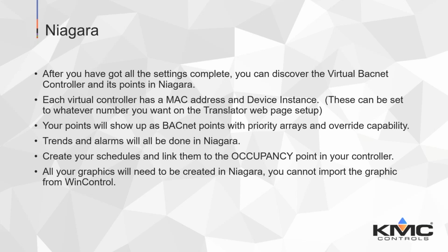So create your schedules and link those to your occupancy points. Then you're going to have to recreate all your graphics as well. You can't import the graphics from WinControl or reuse those graphics. So all the front end features, whether it's graphics or alarming and trending, really need to be in whatever head end is there, either Niagara or Commander. Yep, you're kind of starting over with your front end.